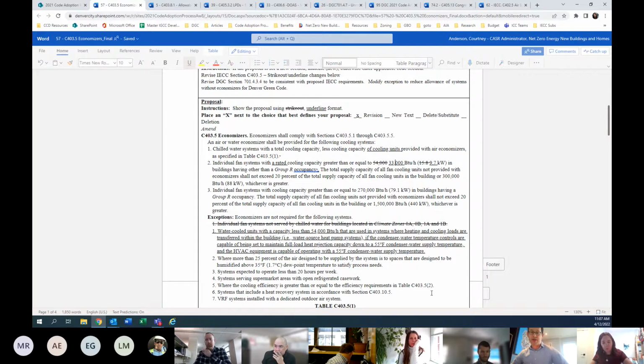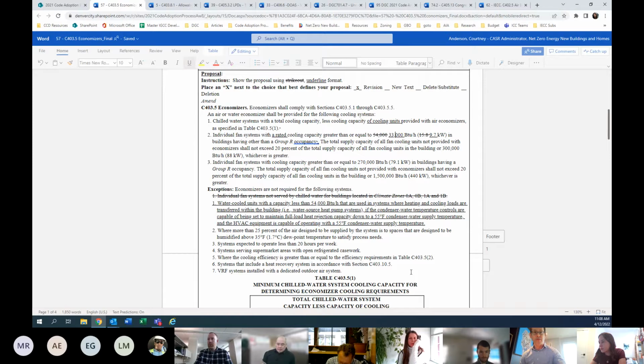For systems with one cooling stage, I've seen it done multiple ways as far as having both integrated and non-integrated economizers. With modern controls, even with a single cooling stage, typically these systems can operate in the integrated mode, which means that the economizer would work in conjunction with compressor cooling. The systems have controls to lock out the cooling when needed.